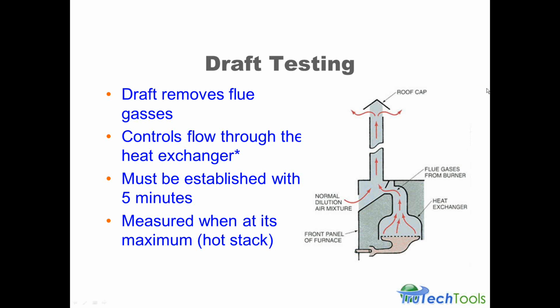Going back to draft testing, because we talked about the importance of proper amounts of dilution air. The draft helps remove flue gases, and this is the case of an atmospherically vented system. Things are different, though, when we talk about condensing or high efficiency systems. It does help control the air flow through the heat exchanger. You can see at the merge point here where the air is coming around the heat exchanger and moving up the dilution air. A blockage or a change in the amount of air moving through the system can affect the airflow over the heat exchanger.